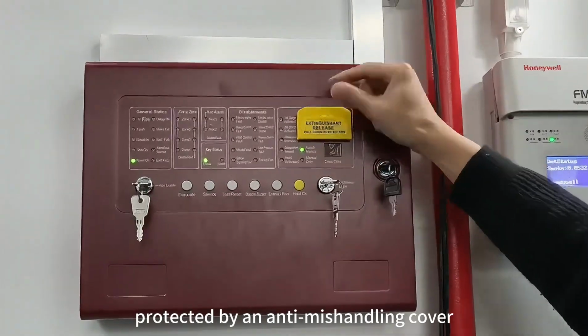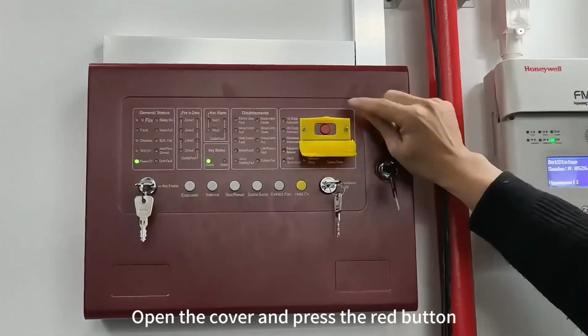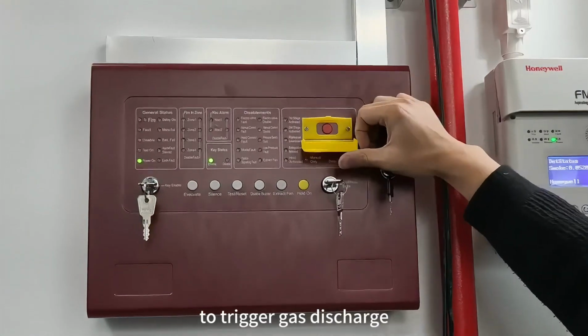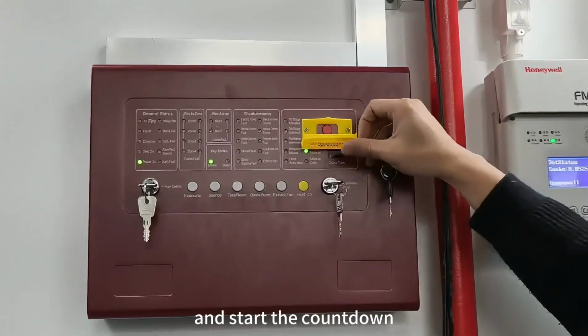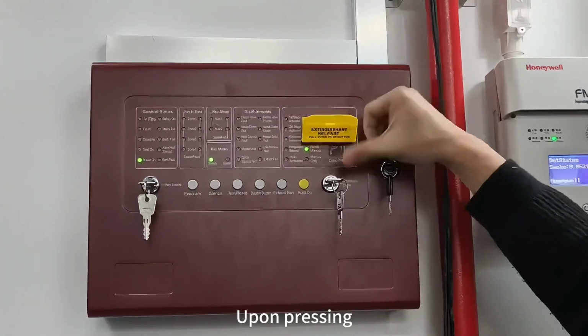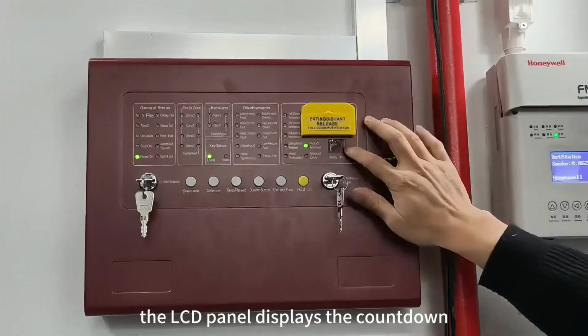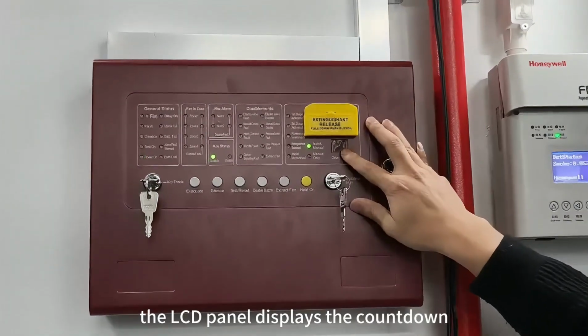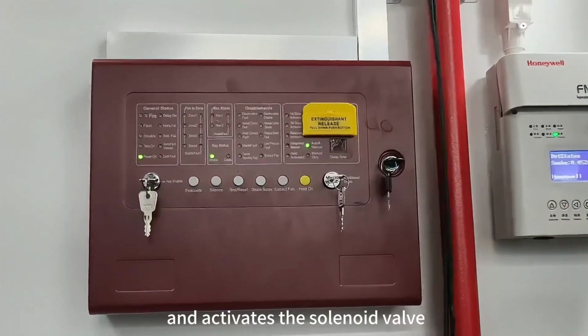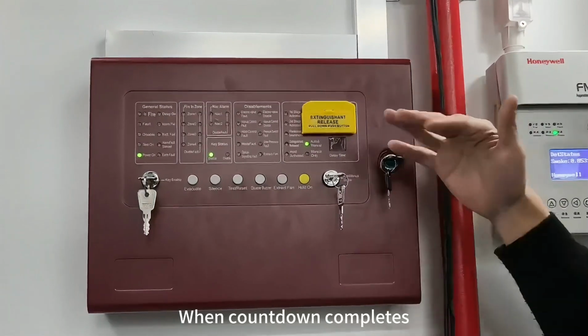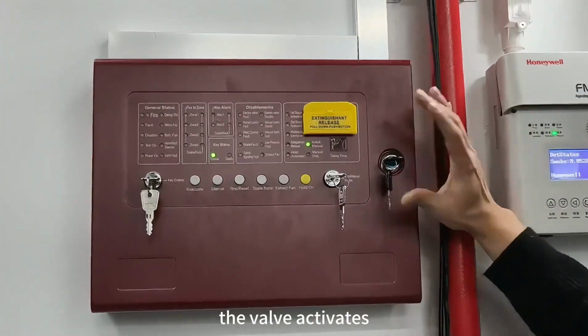It is protected by an anti-mishandling cover. Open the cover and press the red button to trigger gas discharge and start the countdown. Upon pressing, the LCD panel displays the countdown and activates the solenoid valve. When the countdown completes, the valve activates.